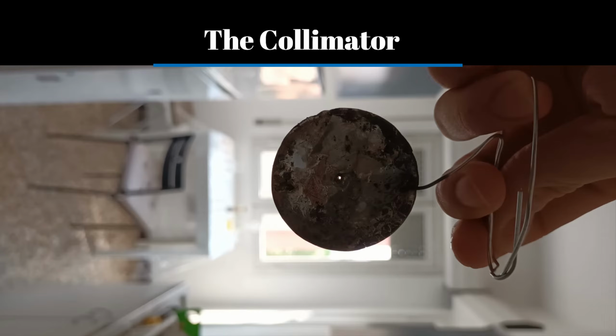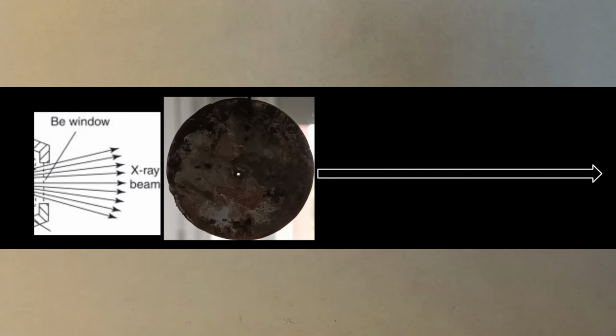So now I'll show you how I designed and how I made my latest model. The job of the collimator is to take a cloud of X-rays that are shooting in all different directions, take only a portion of them and point those needle-like X-rays in one direction.